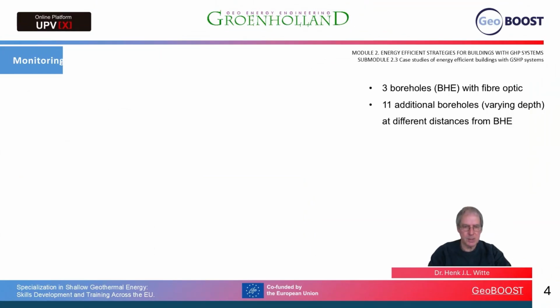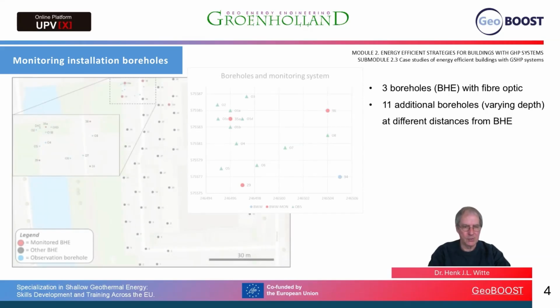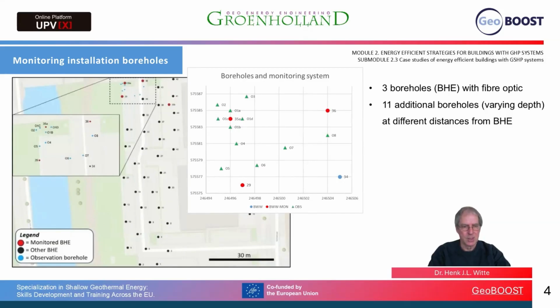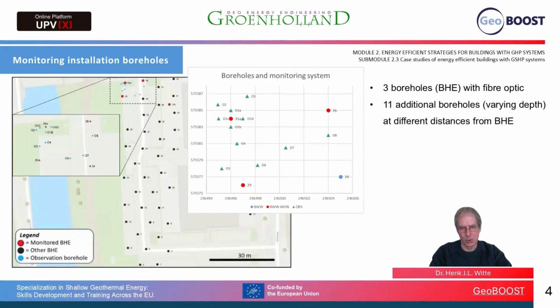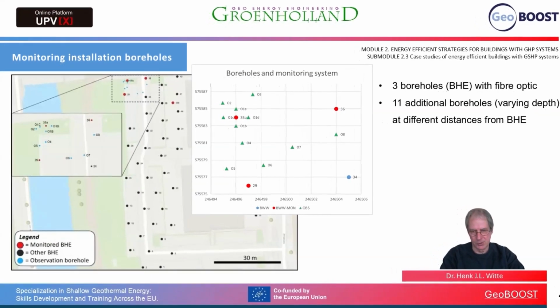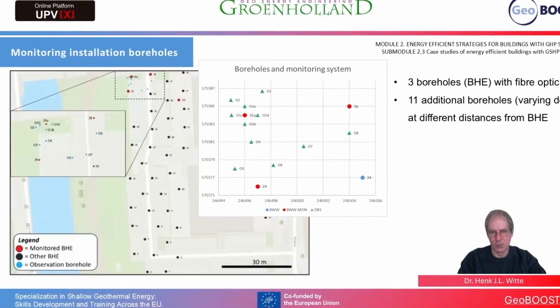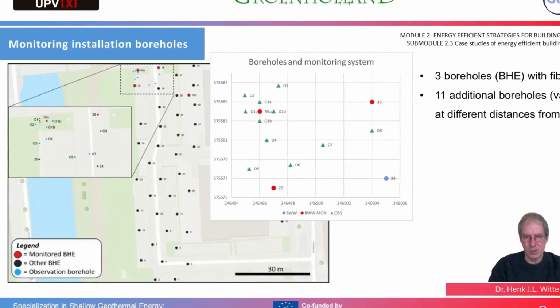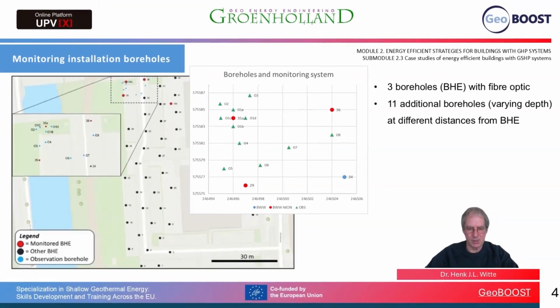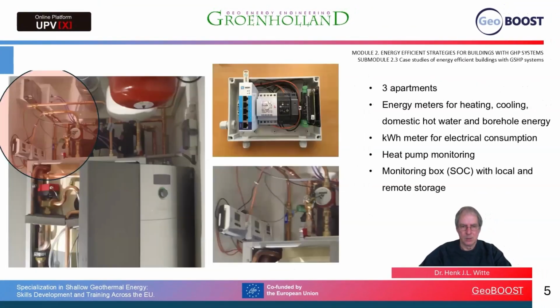Okay, so here we see a more detailed layout of the whole borehole field, with in the call out the actual boreholes that we're going to monitor and the observation points around them. So the red circles are the boreholes that we're going to monitor. The blue circle is another borehole that's not going to be monitored, and the triangles are the observation wells where there is no borehole heat exchanger, but there is a fiber optic cable to measure the temperature.